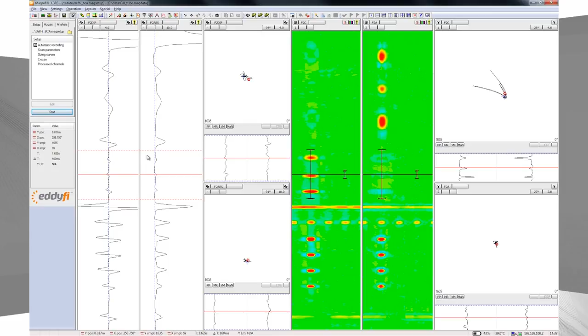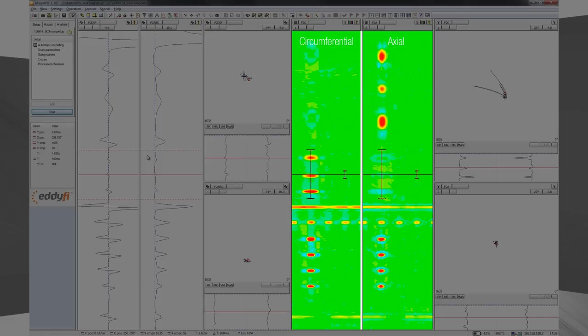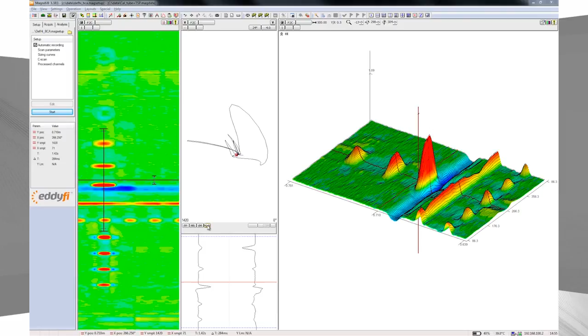Displays standard ASME defects detected with the bobbin probe. But you can also see that the array yields very clear imaging of the axial and circumferential crack-like defects in the form of an easy-to-read C-scan. You can see that the ferromagnetic interference induces a strong negative response, but the defect remains visible. The C-scan clearly shows the circumferential extent of the crack, and the phase is used to assess the depth.